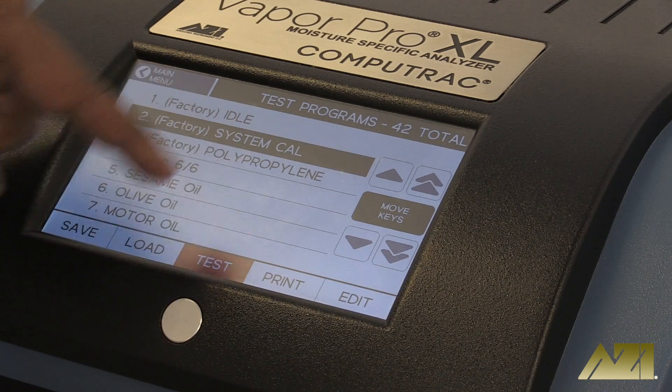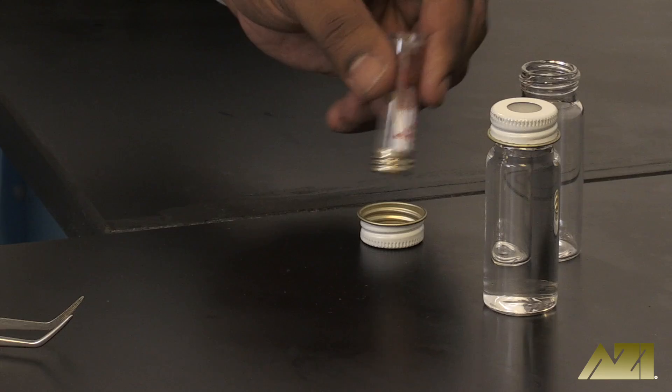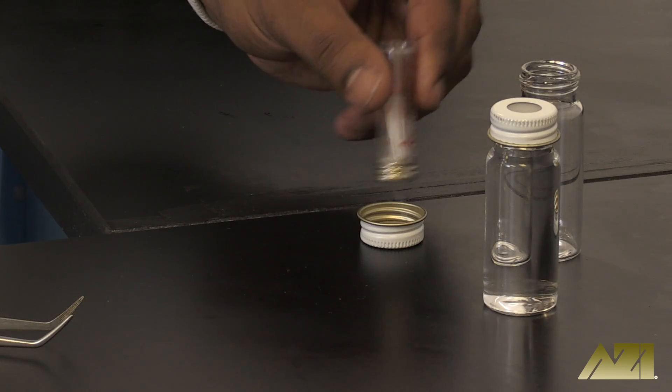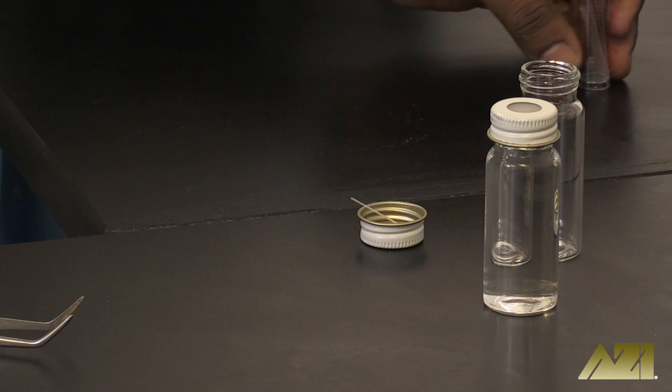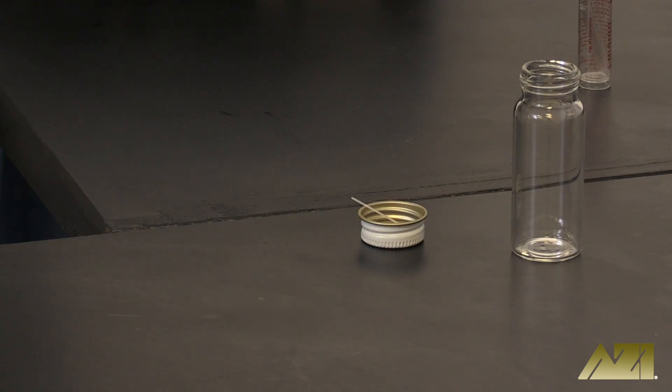To begin, select the test that you wish to perform and allow the instrument to reach the necessary temperature. Begin by tipping the tube of one microliter microcaps upside down and shaking gently until a single capillary comes out. Shake it out over the cap of the bottle you will use for the test to make it easier to pick up in the next step.